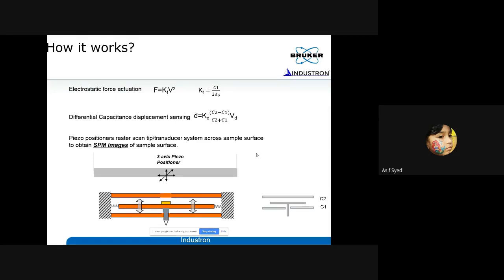Now, if you mount this transducer that I just mentioned on top of this piezo positioner, you can use it as a scanner. For example, when you scan with X and Y, by applying voltage in X and Y direction of the piezo tube, and by making contact with this transducer onto a surface, as the transducer slides in X and Y direction, it is going to feel the surface roughness, ups and downs and bumps, and then the transducer will move up and down, that you can measure as a voltage. Now, if you do this line by line, you can create a 3D topography of your surface. That is the advantage of this system.